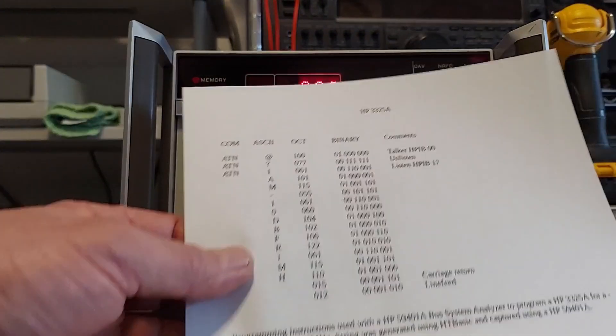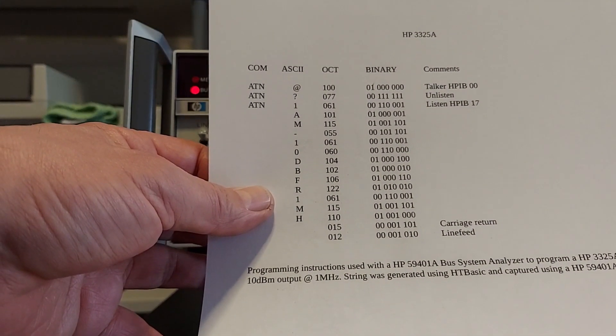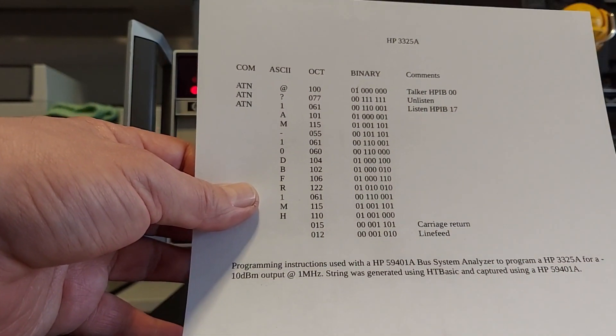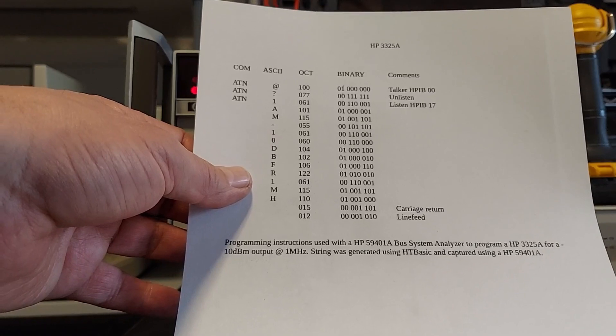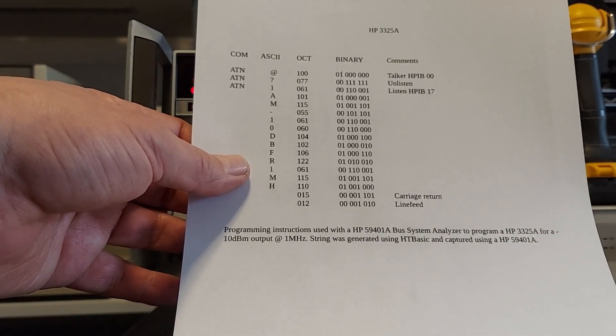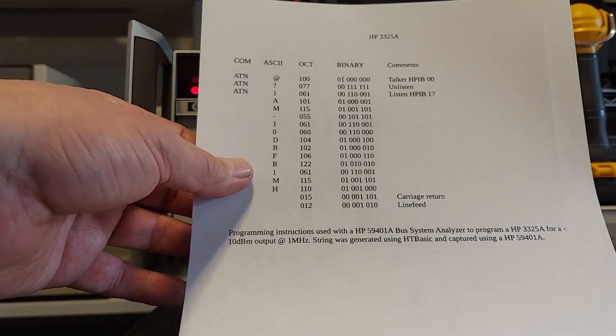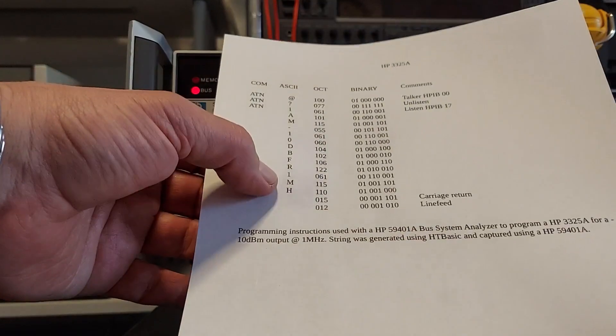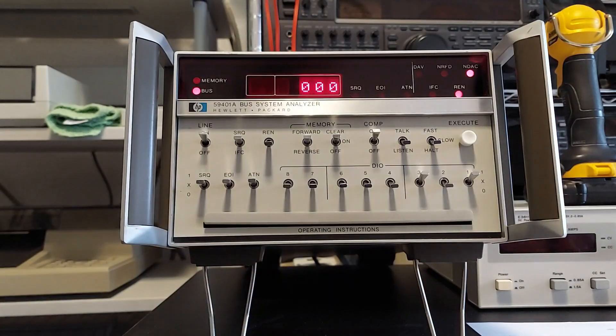Today I'm going to go through how to set this instrument up and program it. This is a bus capture I did using this instrument - commands sent using HTBasic. It is setting the HP 3325A to an amplitude of minus 10 dB and a frequency of one megahertz. I'm going to go through the steps of toggling all this in and sending it out on the bus and showing the results.